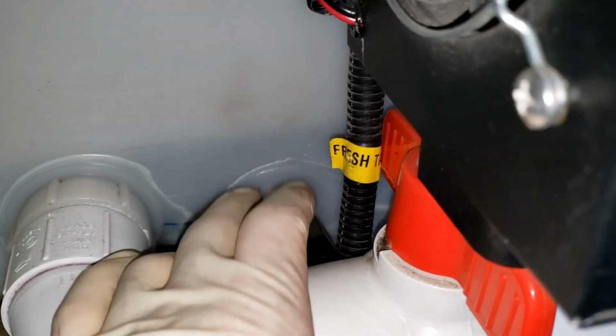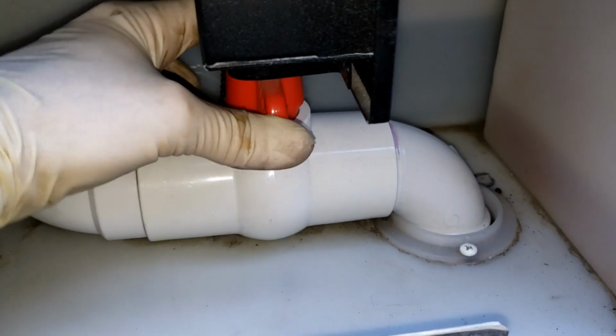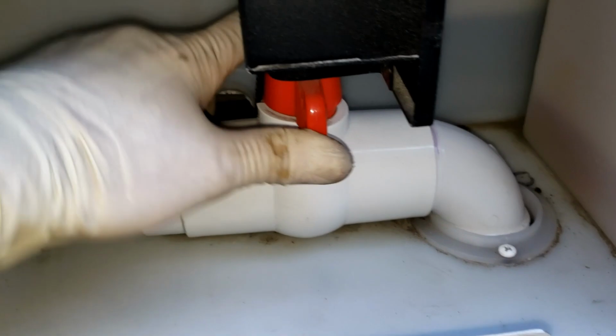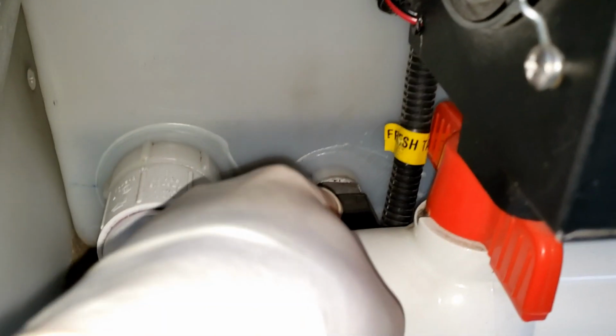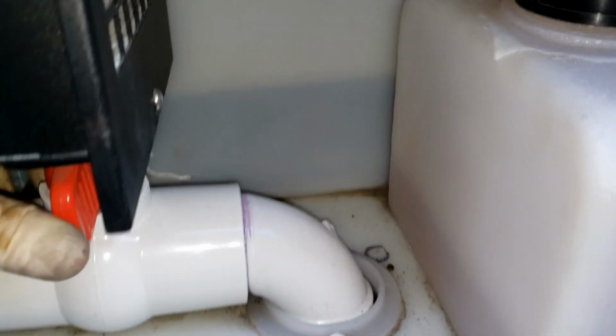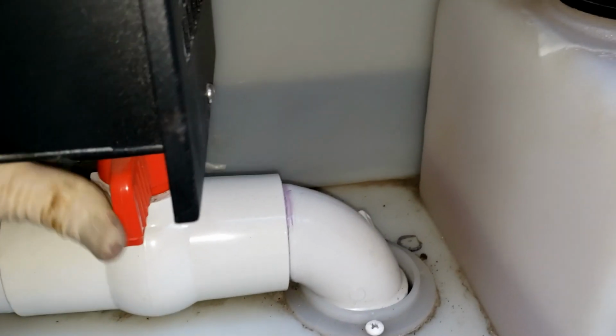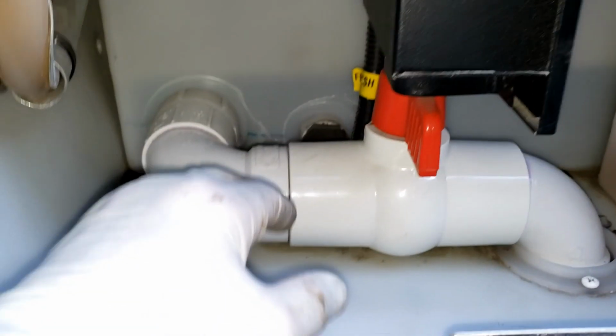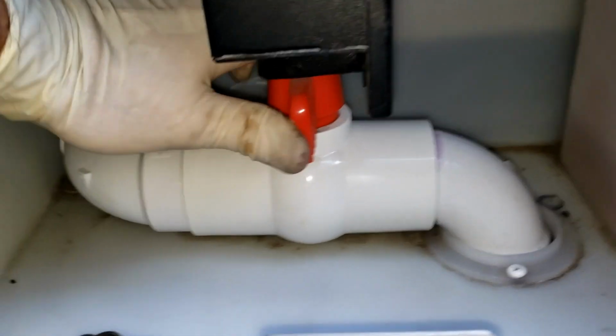It's just a pressure sensor. So the first step is to drain the water out, because we have to pull that sensor out, and when we do, all the water's going to run out. That also gets us ready for the next step, which is after the sensor is replaced. So we're just going to open up the drain and let it drain out right there.